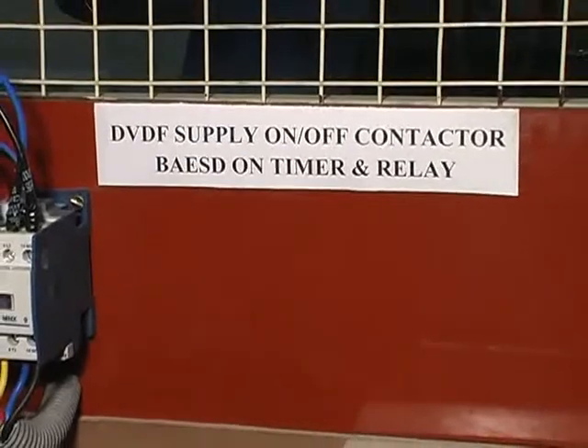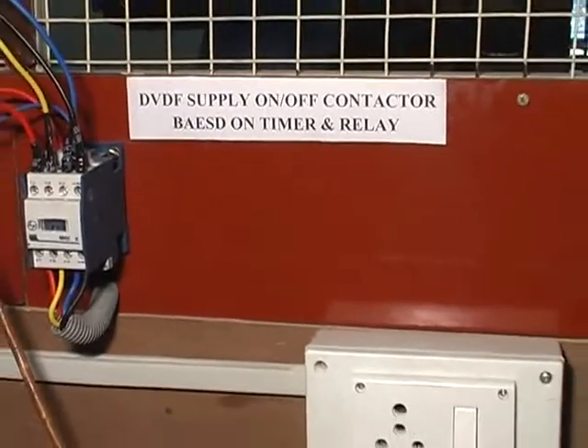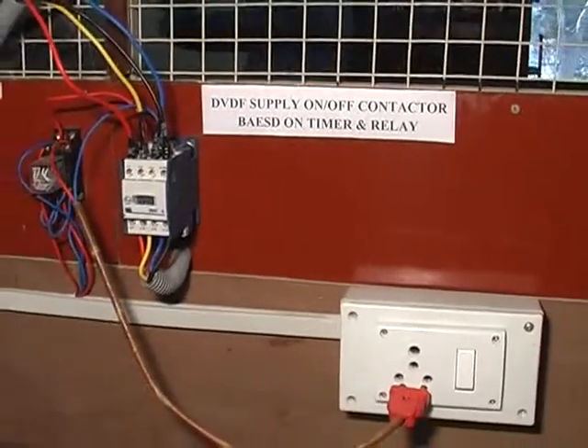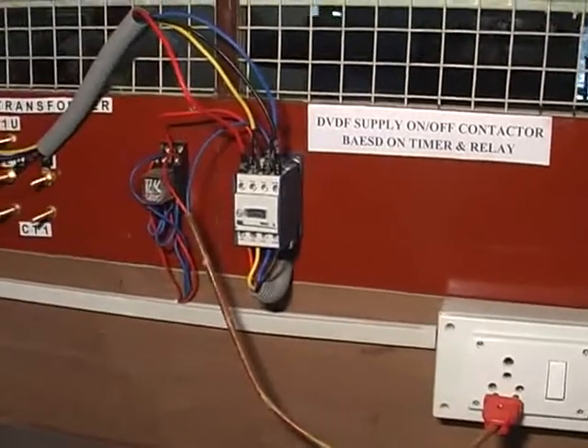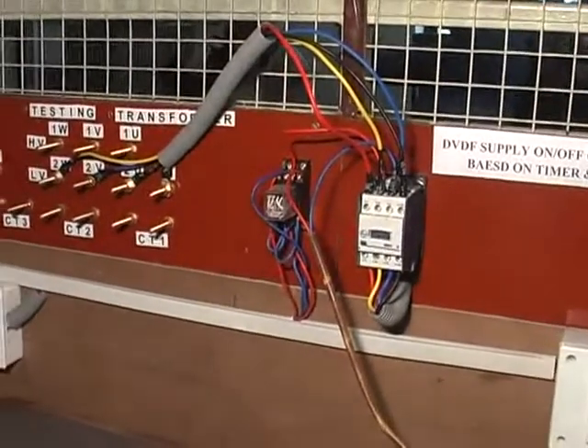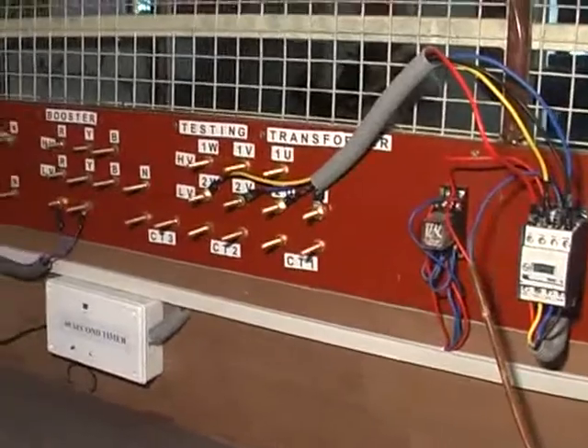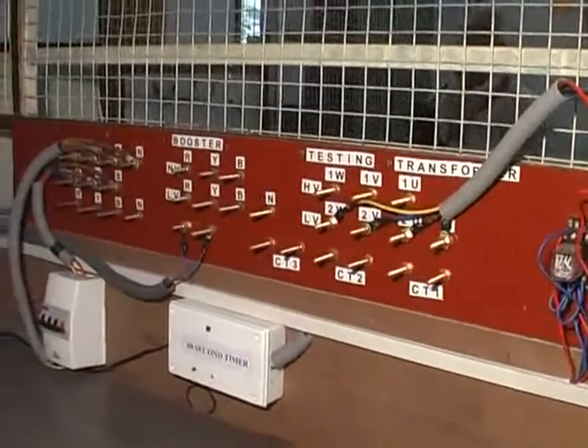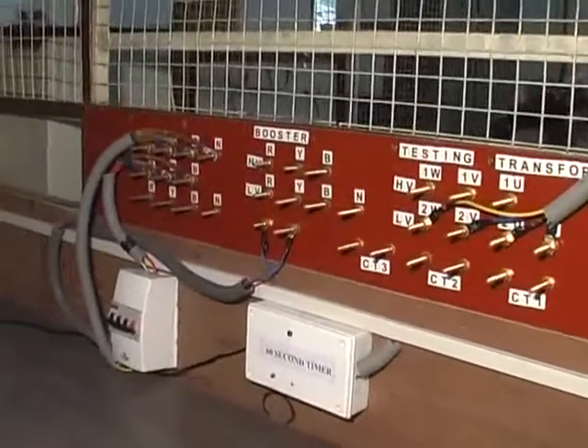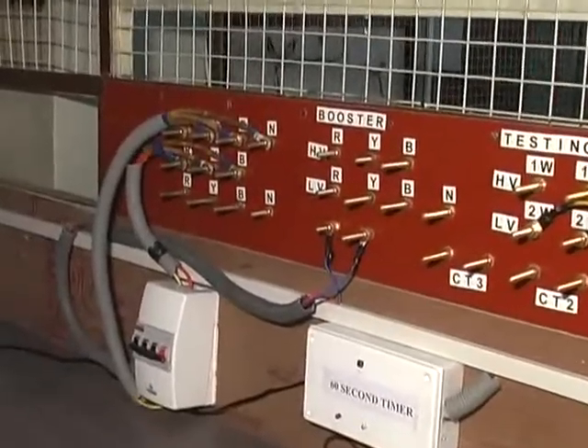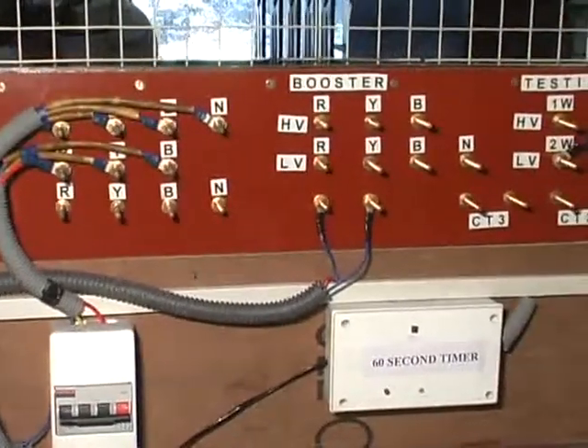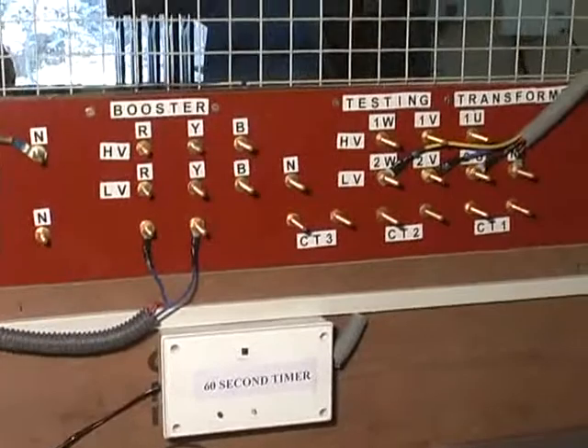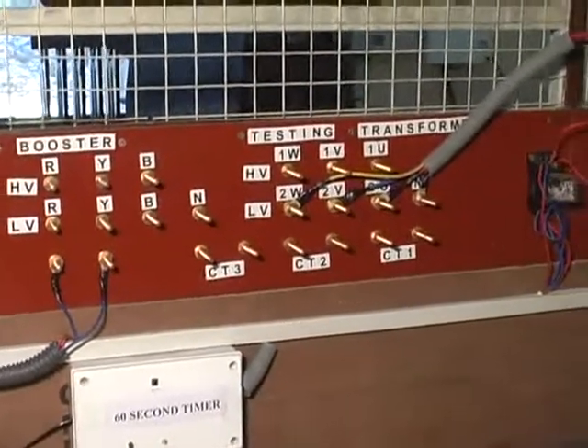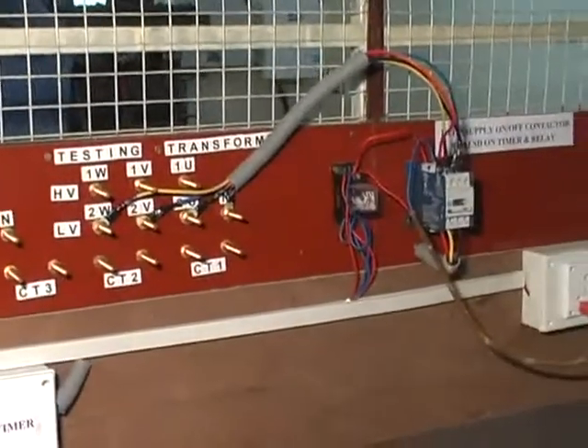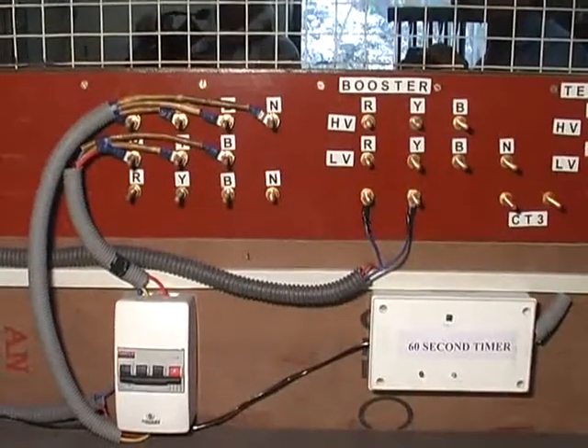This is a protection arrangement which has been designed and fabricated in the institute. As per IS requirement, 60 seconds is the time for which the high voltage and double voltage double frequency test is to be conducted. This arrangement automatically cuts off the applied voltage after a lapse of 60 seconds time.